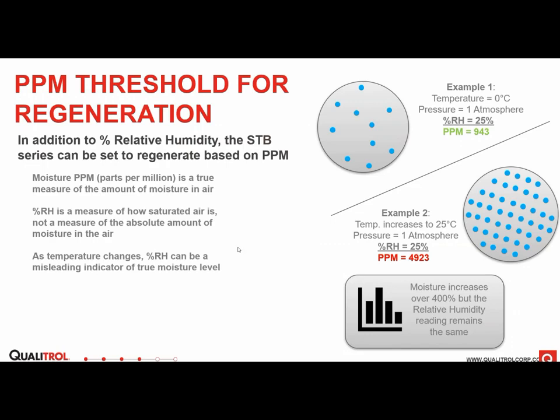So let's talk about the ppm, parts per million of moisture regeneration threshold. We wanted to add this because RH isn't always the best indicator of moisture in the desiccant chamber. Moisture parts per million is a true measure of the amount of moisture in the air, whereas RH is a measure of how saturated the air is, not a measure of the absolute amount of moisture in that air. So as temperature changes, percent RH can be a misleading indicator of the true moisture level.